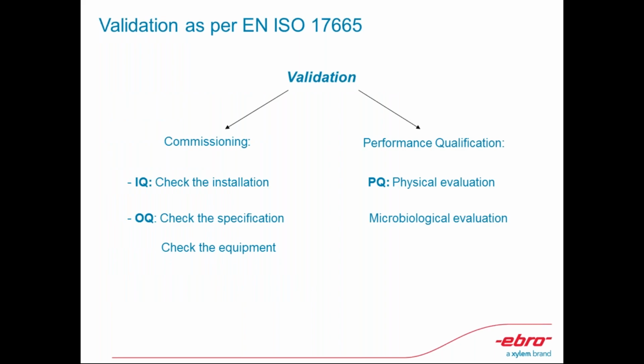Now here we go again with IQ, OQ, and PQ, because it is also mentioned by the ISO 17665. To your left, the commissioning refers to new equipment, and this also includes refurbished equipment. And then to the right is the PQ, which is a cycle that completes the IQ and OQ, but it is also valid for already used autoclaves in the hospital CSSD units.